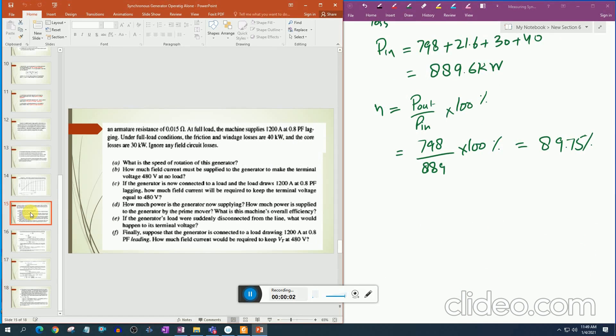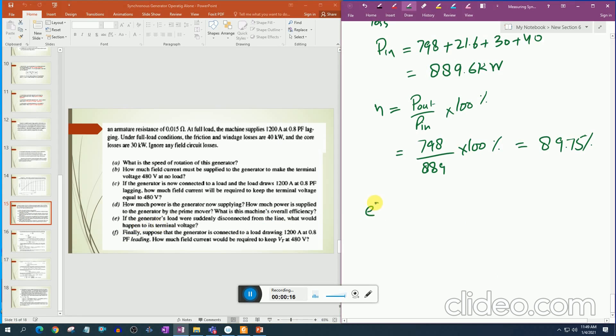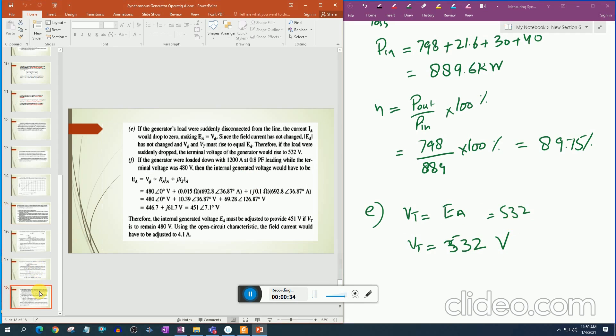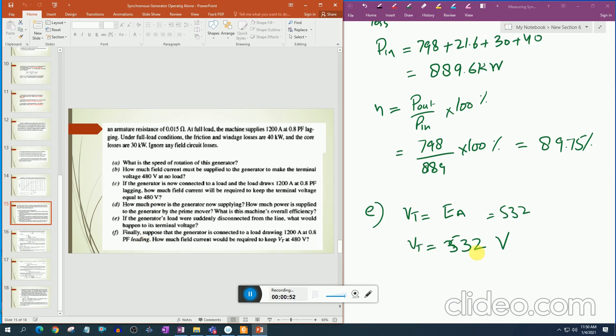Part e: If the generator load is suddenly disconnected from the line, what happens to the terminal voltage? If the load is suddenly disconnected, Ia drops to zero, making Ea = V_phase, so the terminal voltage rises to equal Ea = 532 V.